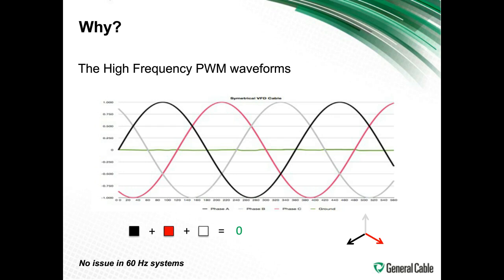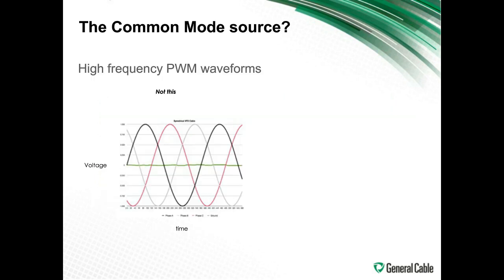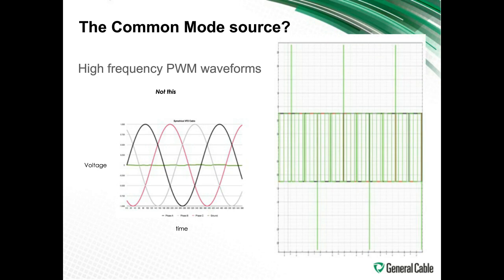Why does this happen? Here we go again with that high frequency pulse width modulation waveform. You see, with 60 hertz systems, you have the phases all 120 degrees apart. You have a three-phase voltage waveform. And in this, because the phases are 120 degrees apart, they all cancel each other out. And that's a 60 hertz system. With the common mode source, like you have with the pulse width modulation from a VFD drive and the high frequency, this is not what you see. What you see is a digitized square wave that we're trying to create an AC, a pseudo-AC form from.